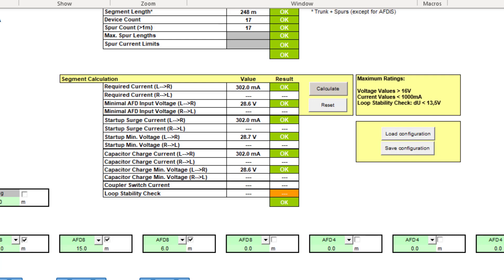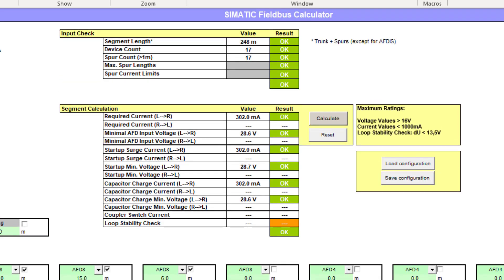If you're using the DP to PA link coupler, it's going to help you. If you're using the transparent, I wouldn't recommend putting more than 25 devices on each one of the transparent couplers to keep a nice stable network. You can go up to 31, but from my experience, I'd like to keep it lower than that. I'll put the link for that in the comments.